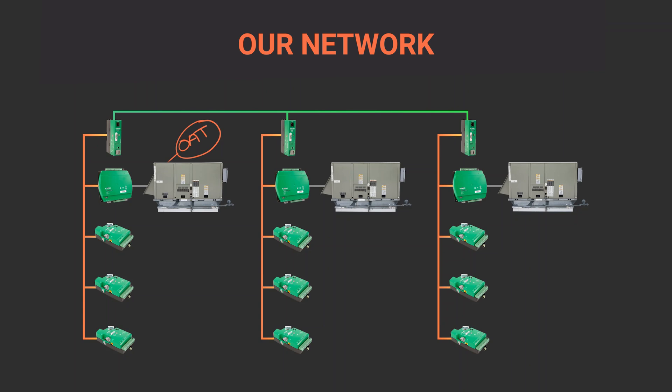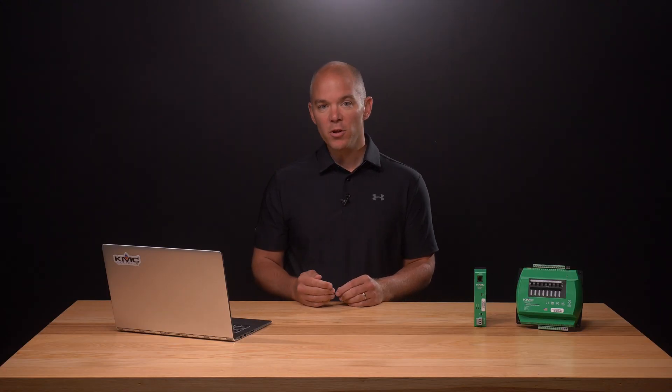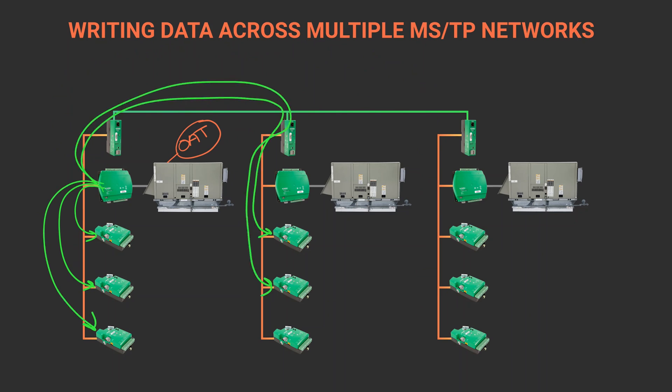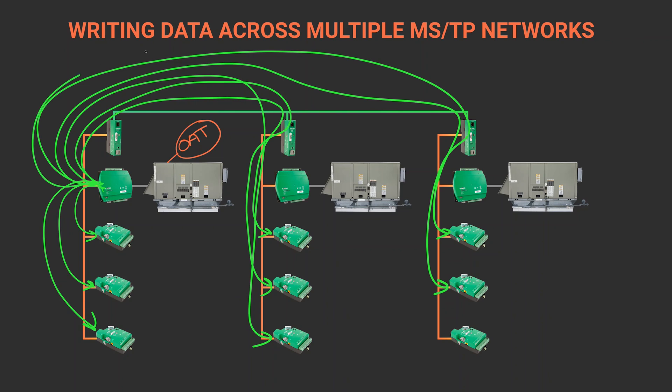Here, we have multiple air handlers and VAVs on multiple MSTP networks, all connected with routers. We could push the outside air value with writes from the controller with the outside air temperature sensor to all the controllers in the system. Given the number of VAVs in the system, this would be a large program and create a single point of failure for point passing.